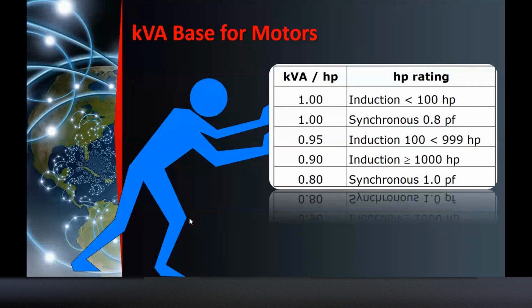Sorry. Okay. So in short circuit calculation, actually, to be conservative in my calculation, since I am in industry, when I calculate to get a conservative result, I use 1 kVA equals 1 horsepower, or rather 1 horsepower equals 1 kVA. But we know that 1 kVA is not always equal to 1 horsepower because we have a formula for that. So to be conservative, that is what I use, which you can use because it is recommended by IEEE. Okay? That is the IEEE approach.